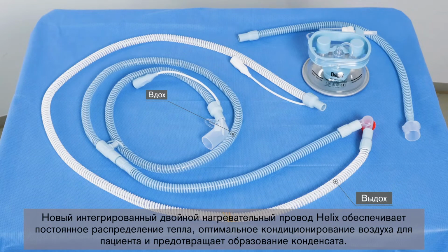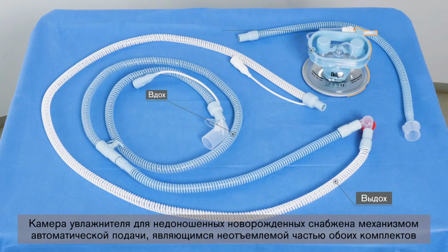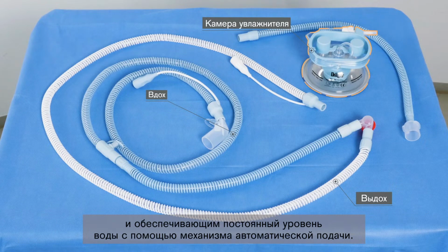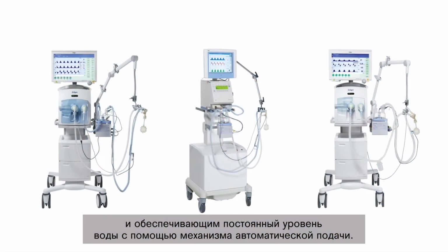The newly integrated double helix heating wire ensures consistent heat distribution, optimal conditioned air for the patient, and prevention of condensation. The humidifier chamber for premature infants has an automatic feed mechanism as an integral part of both sets and ensures a constant water level by means of an auto feed mechanism.